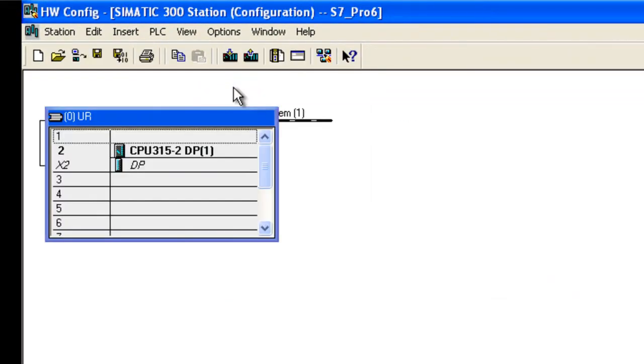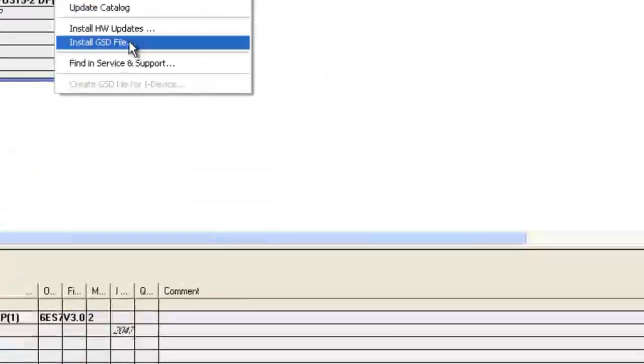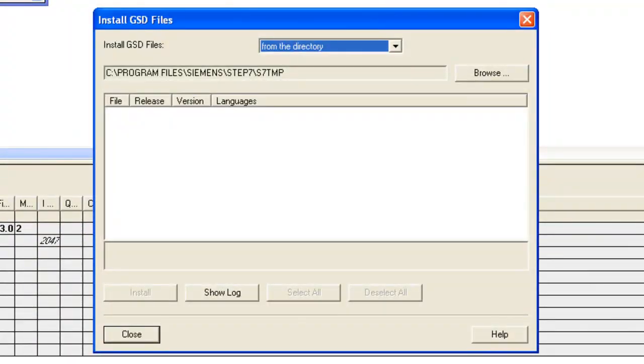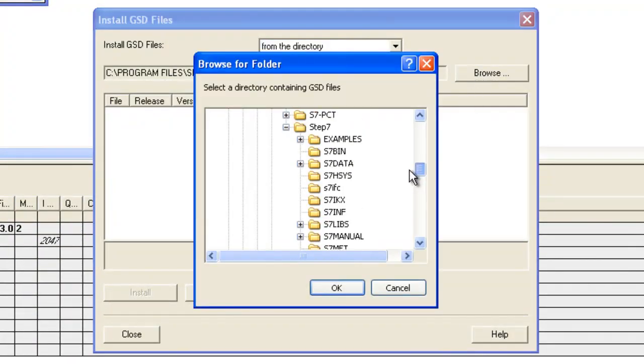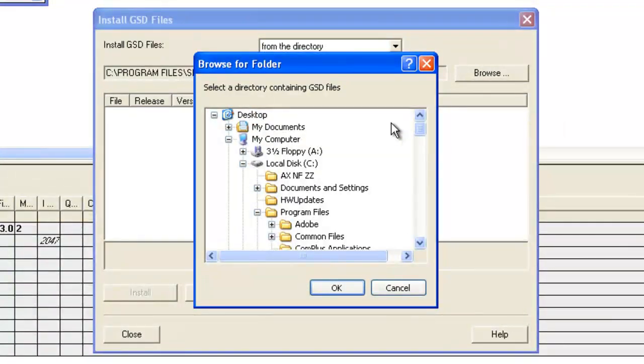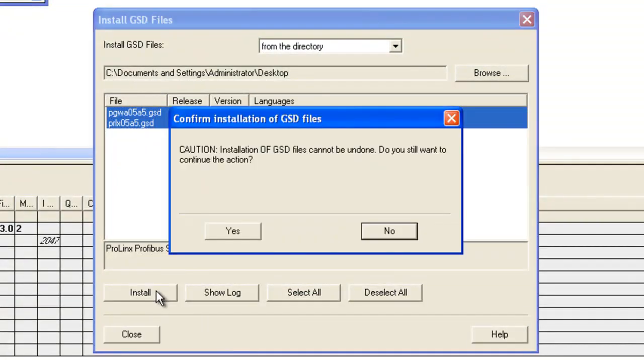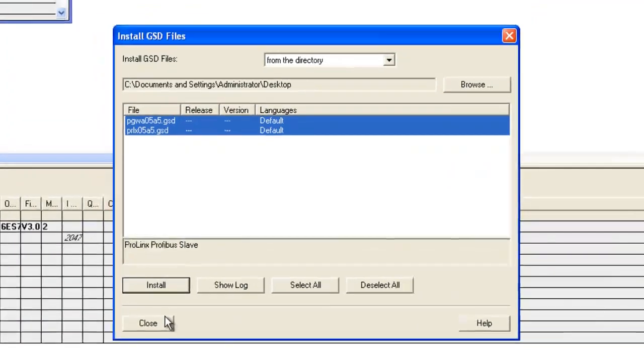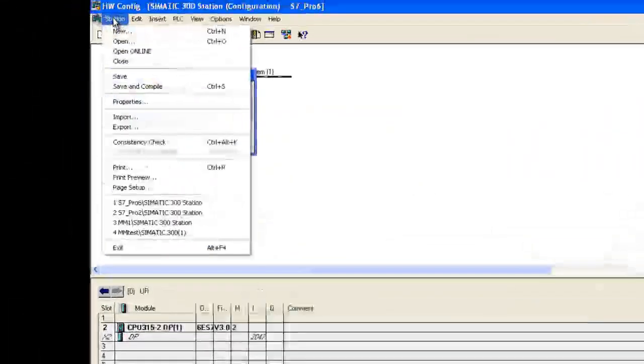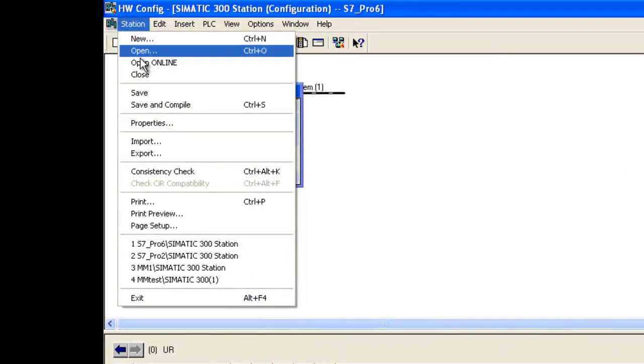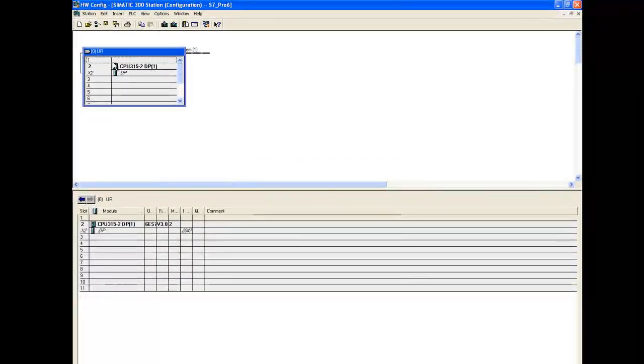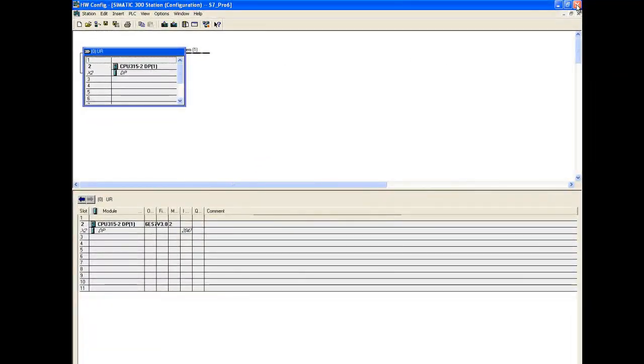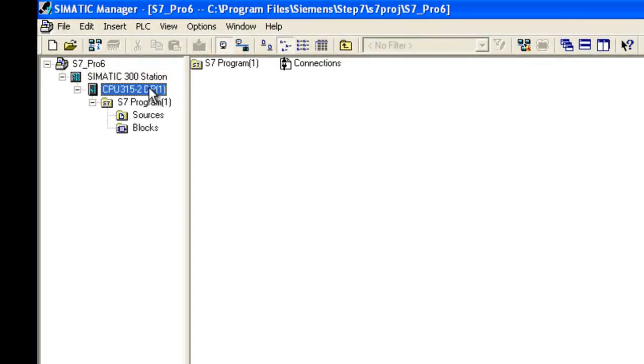Now here is where we're going to add in the GSD files. So we'll go Options, Install GSD File. And we're going to browse. I stored my GSD files just right on the desktop. So that's what we're going to select. And we're going to grab both these and install them. Click Yes. And now we'll go Station, Save and Compile. This will save my changes. And we'll go back to the actual Step 7 program.